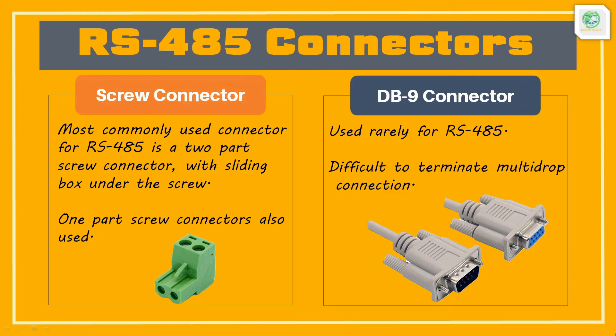The preferred connector is the two-part screw connector with the sliding box under the screw, as shown in the figure. Manufacturers sometimes use the DB9 connector instead. The DB9 connector has problems when used for multi-drop connections, as the RS-485 multi-drop system requires the connection of two wires so that the second wire can continue to the next device. This can be achieved simply with screw connectors — two wires can be twisted together and inserted under the screw — but with a DB9 connector, the two wires must be soldered together with a third wire, which is then soldered onto the pin of the DB9 connector.